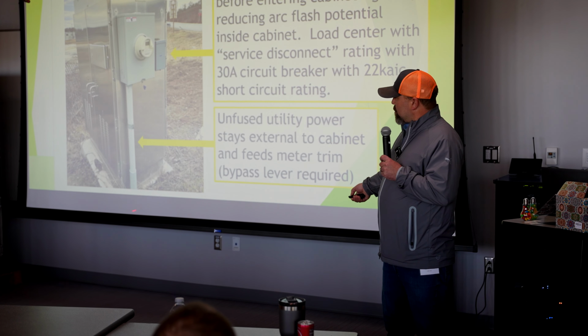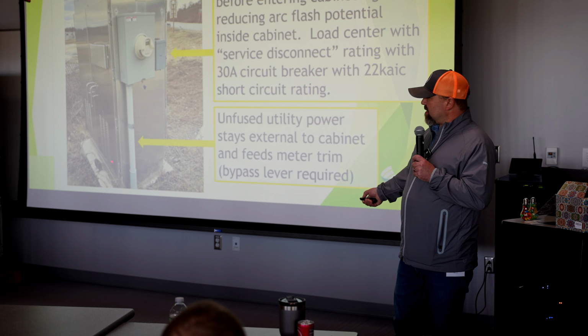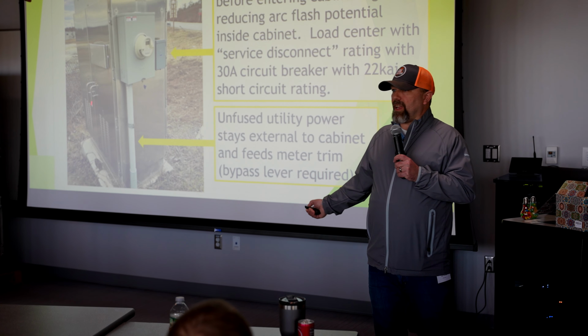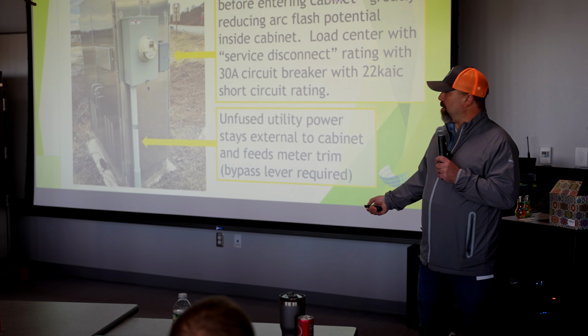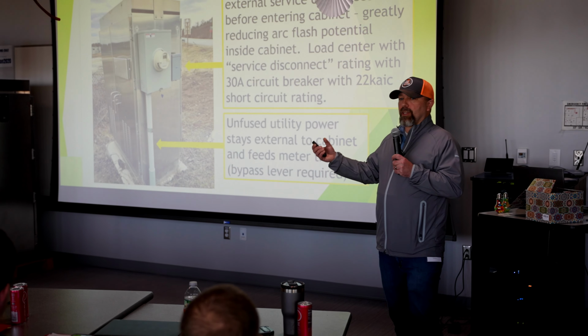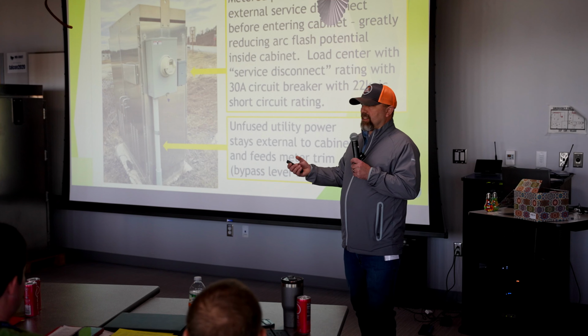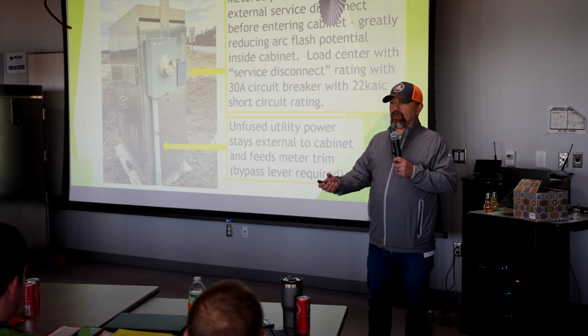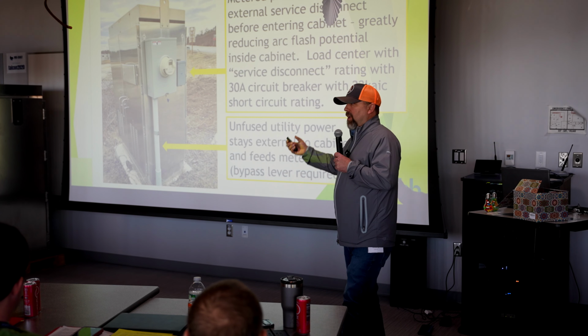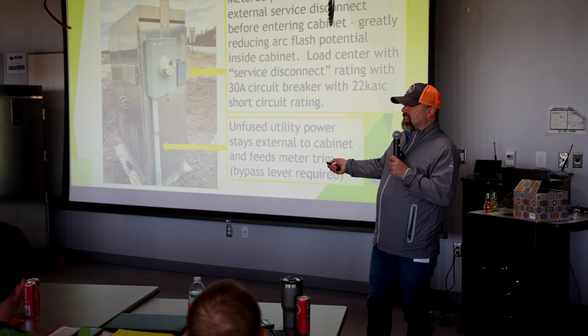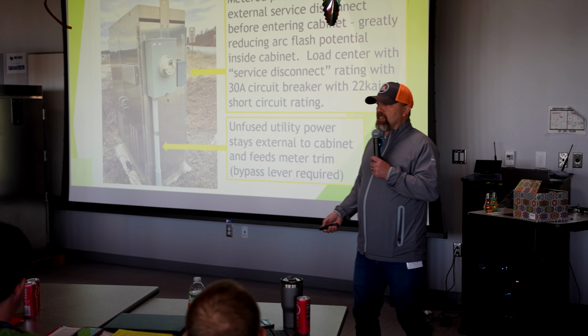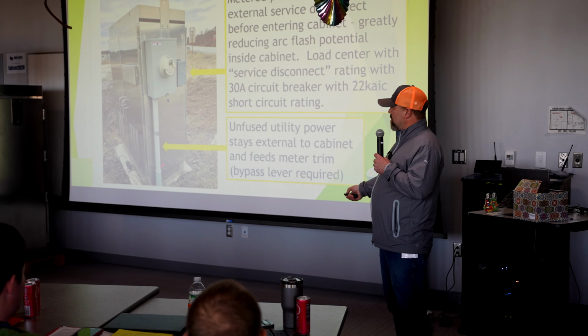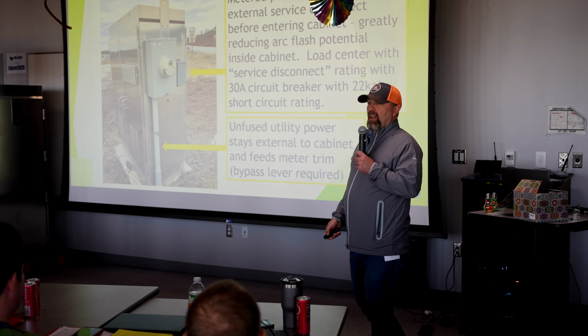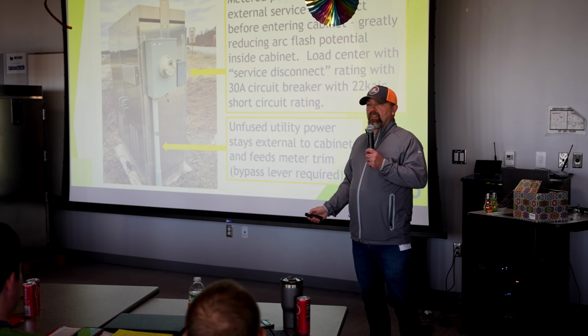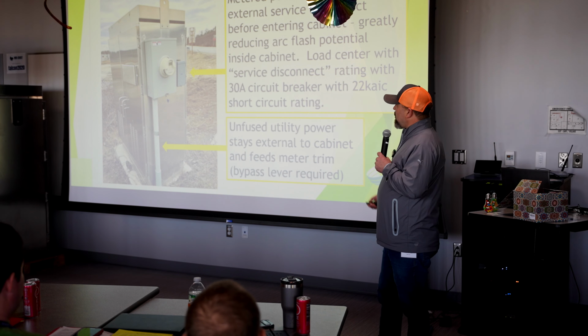I'm still seeing some cabinets where they're bringing that conduit inside the cabinet foundation and they're sleeving it in liquid tight. So technically you are creating a barrier between that utility power and the inside of the enclosure, but the spirit of the policy is that they want to start seeing that run on the outside so that it doesn't enter the cabinet at all.